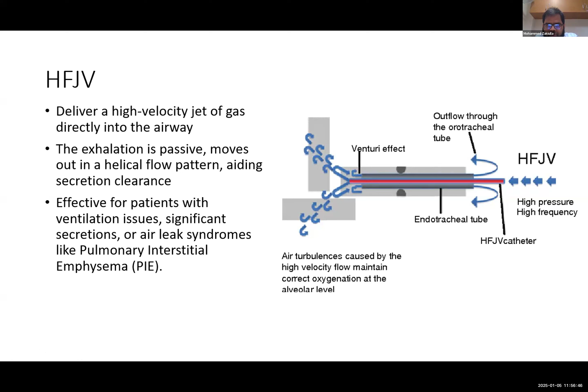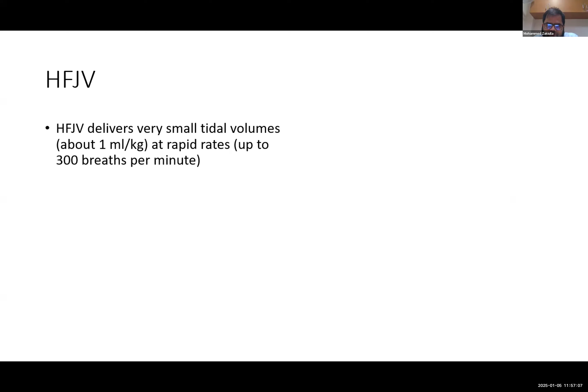Here again the concept is the same. It delivers very small tidal volumes, around 1 ml per kg, 1 to 1.2, and we are using very rapid rates up to 300 breaths per minute. Because we are using such rapid rates, the inspiratory time is very short, around 0.2 seconds. If you are using 300 breaths per minute, 300 breaths in 60 seconds, then for one breath it will be around 0.2 seconds. That is very short.